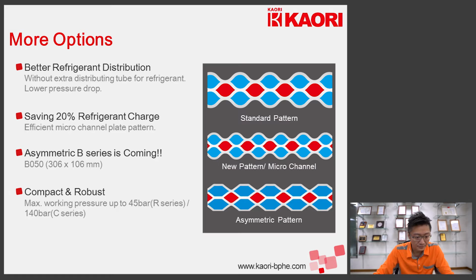And the third pattern is the so-called asymmetric pattern. It allows one side to be smaller than the other. So it keeps the benefit of microchannel with less refrigerant charge while keeping the water side with bigger volume, so the pressure drop can be limited. The asymmetric is still under development, but we will have an announcement for its release very soon. Please stay tuned for the updates. And last but not least, all patterns can be constructed in a robust way, so they can handle up to 140 bars for CO2 applications.